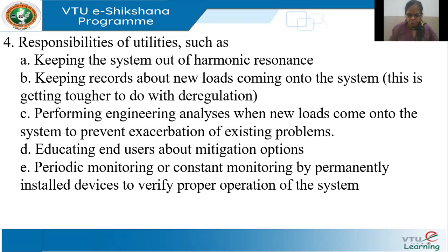For example, supposing I'm installing a power factor capacitor bank for power factor improvement. Clear? And at that point, there is a transformer. Let us say the transformer and the capacitor together form an RLC circuit, and the resonant frequency is 250 hertz. Clear? 250 hertz is the fifth harmonic. Now, when I connect a load, fifth harmonic currents are very common in many loads, and so they will get amplified because of this resonance, and the outcome would be my capacitor will fail.